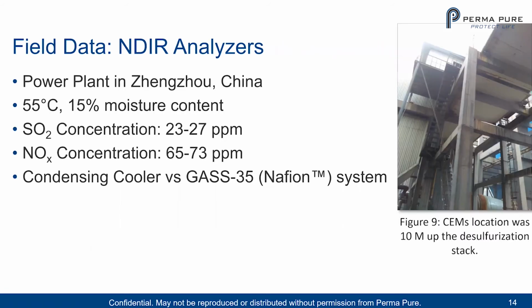So let's look at some field data using some NDIR analyzers at a power plant in Zhengzhou in China. This sample was at 55 degrees C with a 15% moisture content. We had an SO2 concentration there of 23 to 27 parts per million, and an NOx concentration of 65 to 73 parts per million. And in this case, we're going to compare the condensing cooler with our GASS-35 Nafion system. Our GASS-35 is a portable system that we can use and bring into the field and get those differences right away.